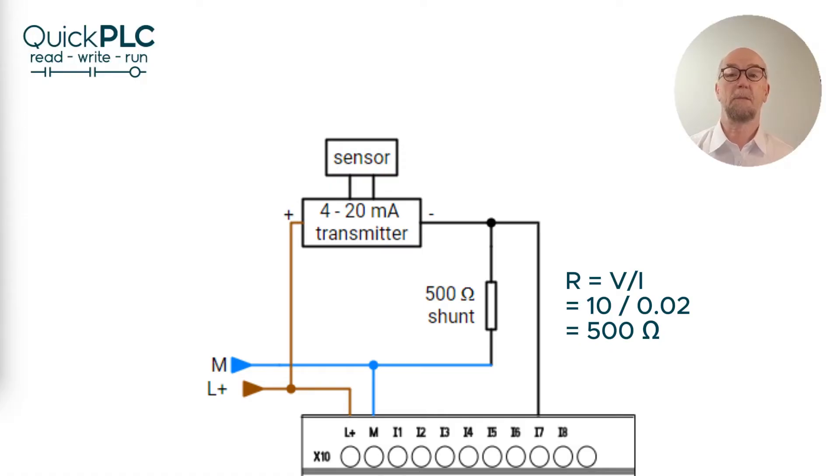This solves several problems for us. We can power the sensor from the loop provided its internal circuitry can work at four milliamps. The 500 ohm input impedance makes the circuit much less susceptible to electrical interference. And we now have what's called a live zero at four milliamps. If a wire breaks we'll have zero milliamps. And some sensors will indicate a fault condition by giving out three or three and a half milliamps. This can be used to generate an alarm in the PLC program.